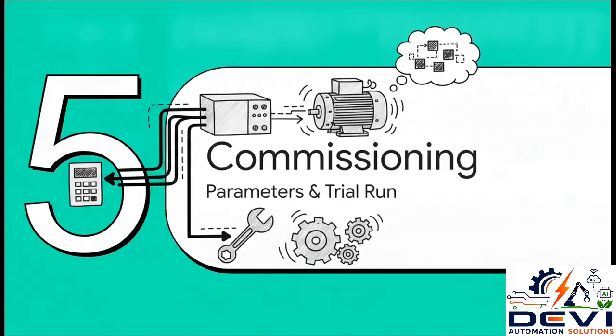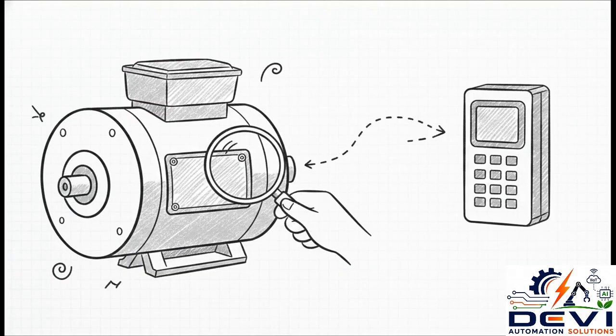Almost there. Section 5. Parameters and commissioning. Look, entering motor parameter settings is definitely not a guessing game. You must take the nameplate directly off the AC motor and input these values exactly as stated. We're talking motor voltage, motor current, frequency, and RPM. Setting your maximum and minimum frequency along with your acceleration and deceleration times ensures the mechanical load isn't jerked around or over-torqued. Getting these motor protection settings right is exactly what stops your motor from burning out when things get heavy.